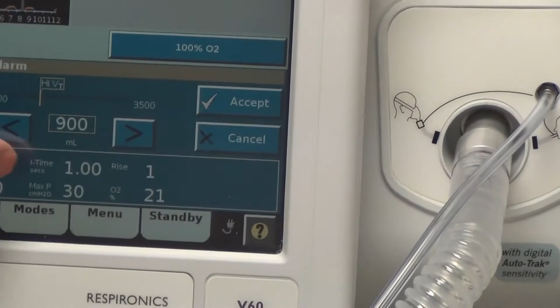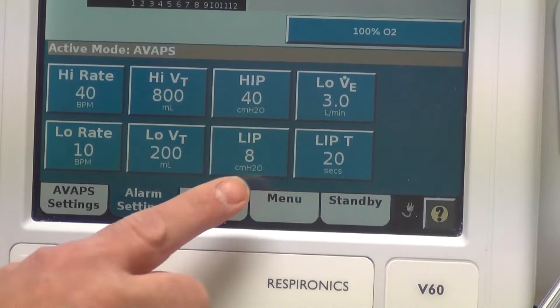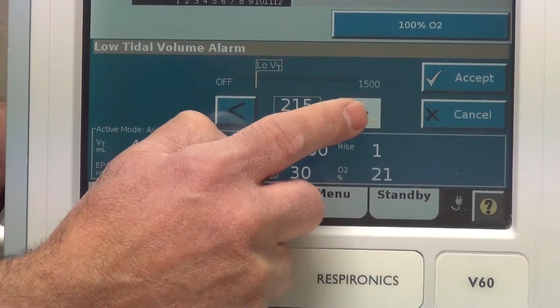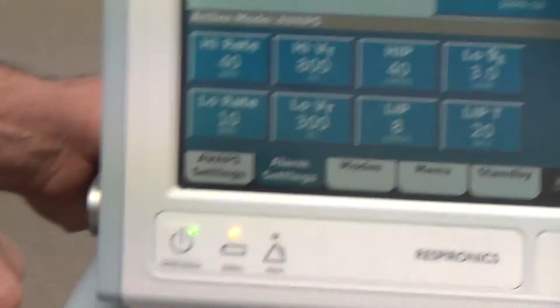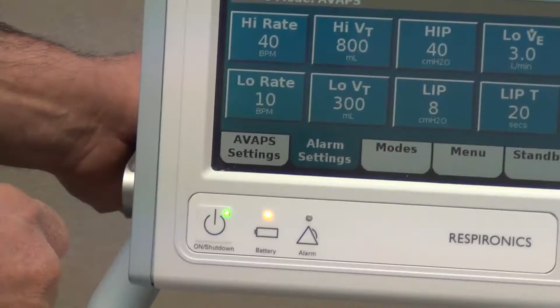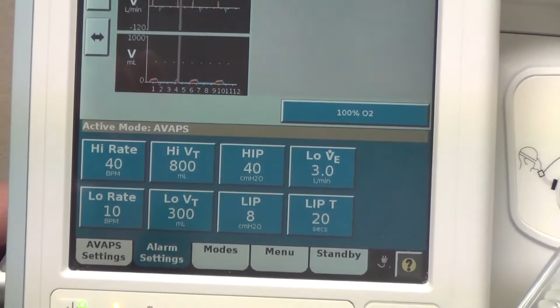We got our high tidal volume, which on our other machine we set to 800. So we can lower this one to 800. There we go. And we'll hit accept. And then we have our low tidal volume, which is 200, which our other machine we set to 300. If you're not taking at least 300 mils, unless you're a really small person, it won't be enough. So this is a good alarm setting. Your high pressure alarm, that is again, like on the other ventilators, what we call the peak pressure alarm. In this machine, it calls it high pressure alarm, or HIP, which we set to 40.